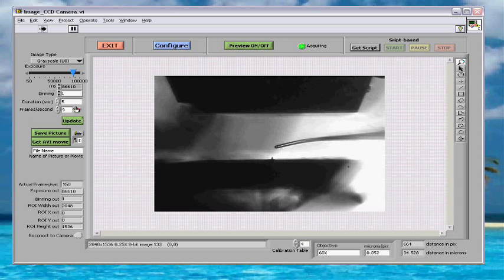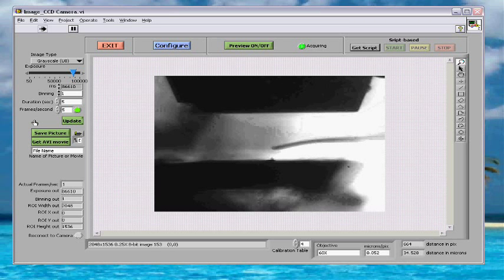When this indicator here turns red, it's because the program cannot keep up with the acquisition rate. So basically you tell them to go at a lower frame rate per second. So now it's going at 5 frames per second, and you see that it can keep up with the acquisition rate, which means that the image is truly 5 frames per second.